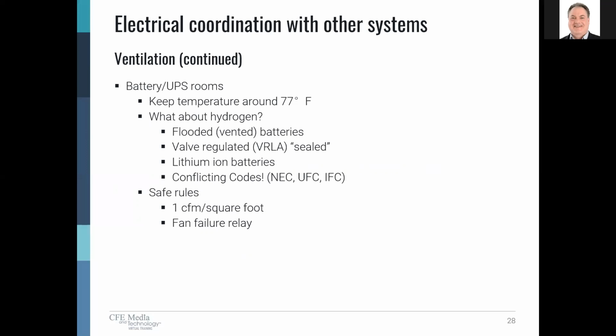Also understand that lithium-ion batteries have different regulations. Fire protection codes are coming out for these types of batteries that are different from those for sealed batteries. A safe rule of thumb is 1 CFM per square foot for UPS rooms. Also understand that often a ventilation fan will be needed, with concerns about fumes from batteries, even sealed batteries. Local authorities may have issues, and you want to have a fan failure relay to know when the room is not being properly exhausted.